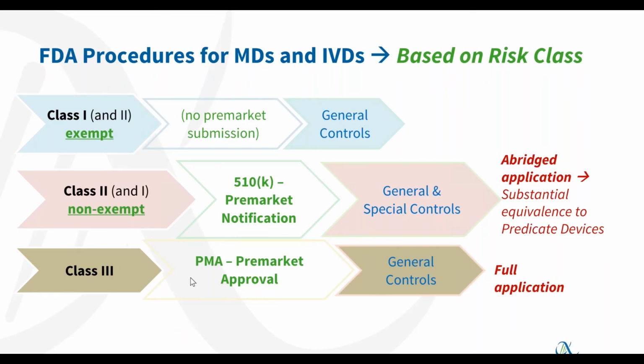In principle, Class 2 devices will most typically be expected to undergo a pre-market notification procedure where FDA reviews some technical aspects. So Class 2 devices or Class 1 devices that are non-exempt of this FDA review need to undertake the so-called 510K procedure, where we need to demonstrate that we comply with general controls, like for Class 1 exempt devices, but also with special controls. And we will see in a moment what special controls mean.